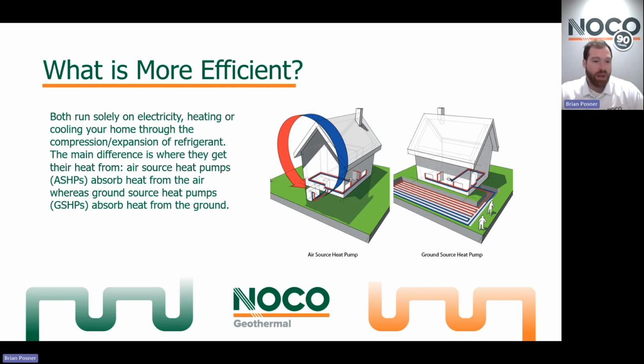Now, what ends up being more efficient? We know that air source heat pumps as well as ground source heat pumps can have coefficients of performance over 1, meaning more than 100% efficient energy exchange. We'll dive a little bit deeper into that. But between what's more efficient, we actually see coefficients of performance around 2 to 3.5 for air source heat pumps, but coefficients of performance between 3 and 6 for geothermal systems.